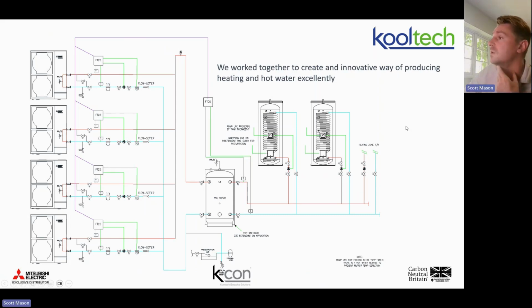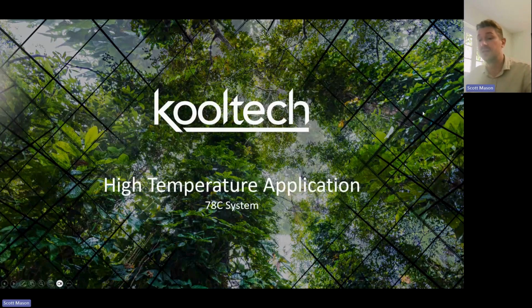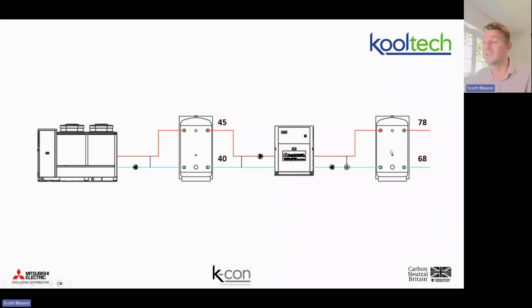And then what we also have a lot of the time is high temperature applications, and lower is obviously better because of the efficiency ratings associated with it. But sometimes this is what's needed just to make a job possible, because it might be that you just can't get into the building in a meaningful way to drop our flow temperatures, and you want to go all electric. So I still need 78 degrees centigrade. Okay, well, that's absolutely fine.